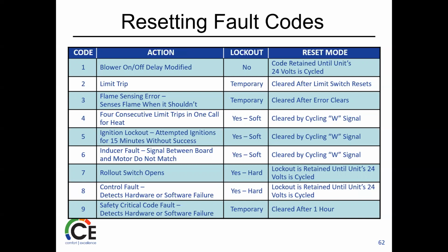Control fault is a hard lockout. Try and recycle the power. If it comes right back, you need a board. And then the defects and the number 9 there kind of goes both ways. Sometimes it's a weird thing that happens. You can reset it again. If you reset it and you get it right back, there's a good chance there's an issue in that board.